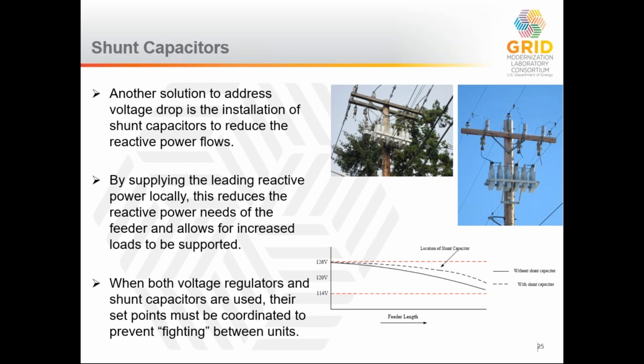So one option is that instead of providing the reactive power all the way from the substation, shunt capacitors can be put out on the circuit near the points of the reactive power load, and these will have the net effect of reducing the current that has to come from the substation and raising voltage a little bit. We often see shunt capacitors near industrial areas where you have large motor loads, sometimes where there are irrigation pumps. Sometimes they're even just used on long rural lines to compensate for some of the inductance of the system. And rural lines also tend to have more pump loads on them.